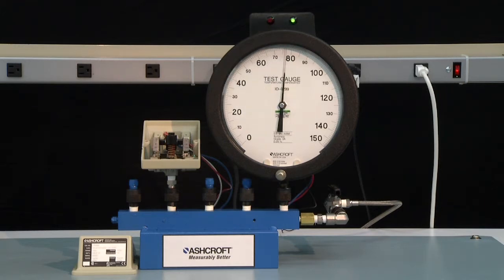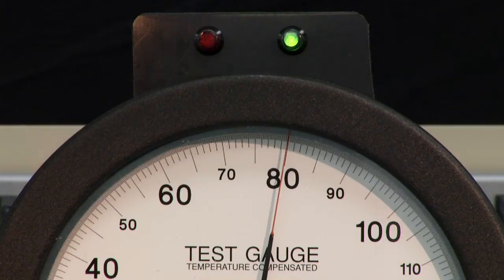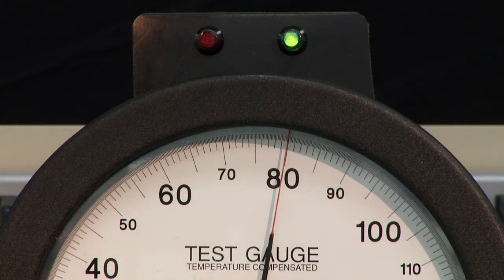You'll note that the switch did turn on ahead of the set point, but that is okay. We are going to adjust it so it will turn off and then turn back on again at the set point. To do that, we set the pressure to the desired set point, 80 PSI.